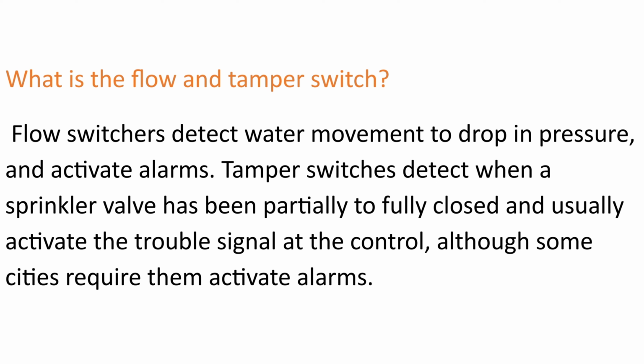What are the flow and tamper switches? Flow switches detect water movement due to a drop in pressure and activate alarms. Tamper switches detect when a sprinkler valve has been partially to fully closed and usually activate the trouble signal at the control panel, although some cities require them to activate alarms.